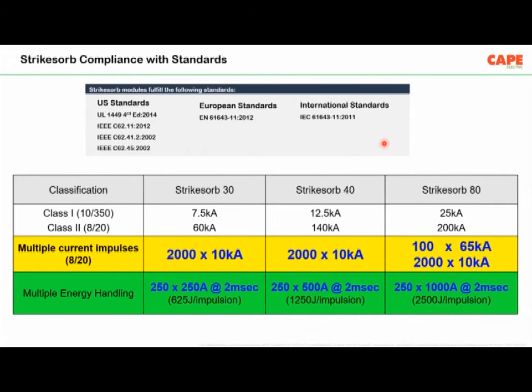If we look at the conventional DIN rail mounted SPDs, these SPDs are tested for one pulse. Then the SPD heats up, the temperature is brought down to room temperature, and then the next pulse is given. That means the testing has a certain cooling down time between the pulses. This is allowed in the standard, but the lightning will not wait until your SPD cools down. It may come quite frequently.